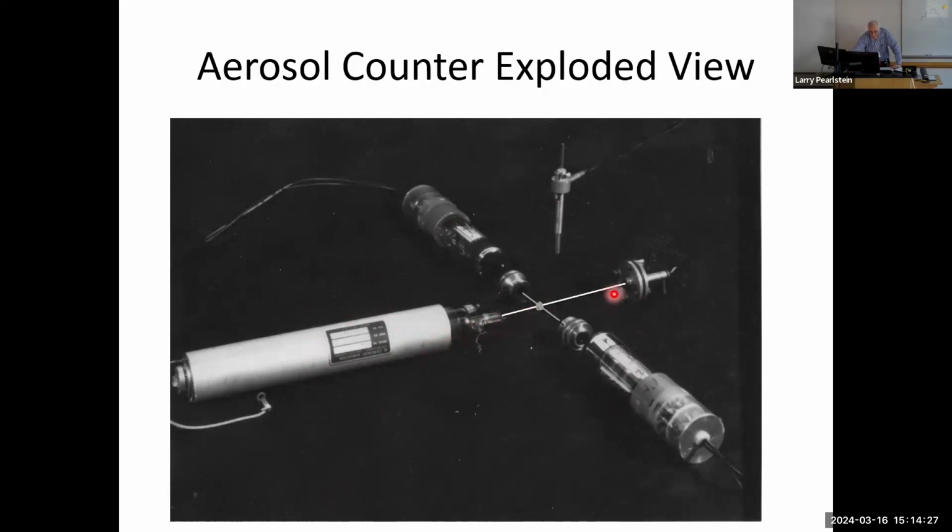This line here is India ink, which in a negative converts to a... Now, the output of these two photomultiplier tubes go to two amplifiers. One is a summing amplifier, and the other is a difference amplifier. The sum gives you the particle size, just as with the other particle counter, but the difference indicates asphericity of the particle as it tumbles through the focus of this beam.